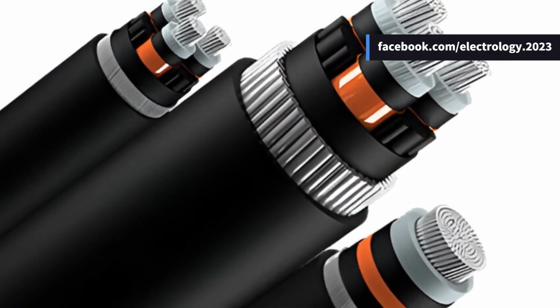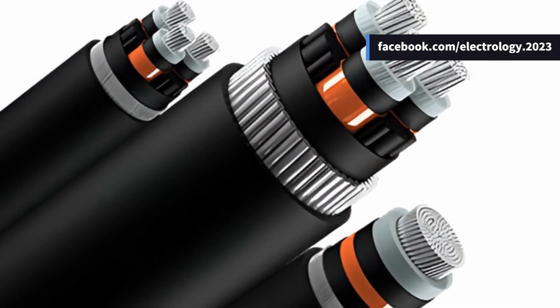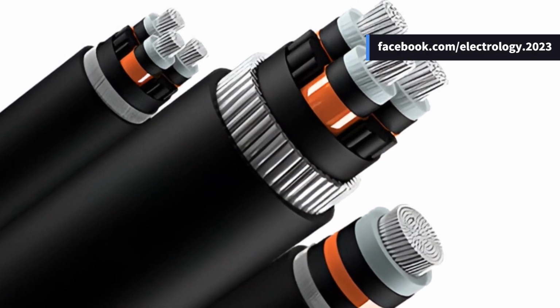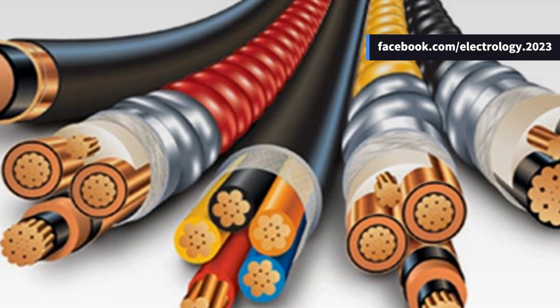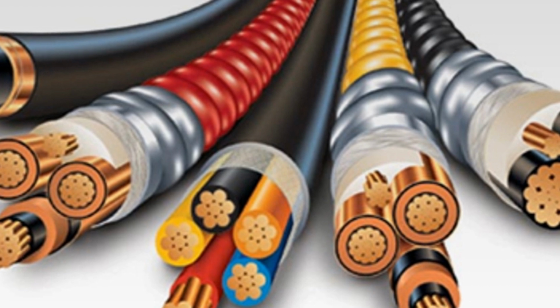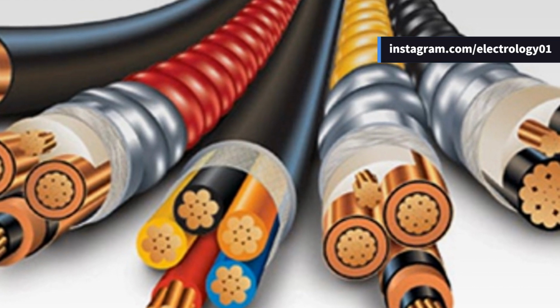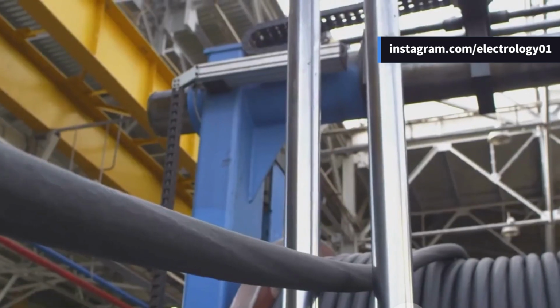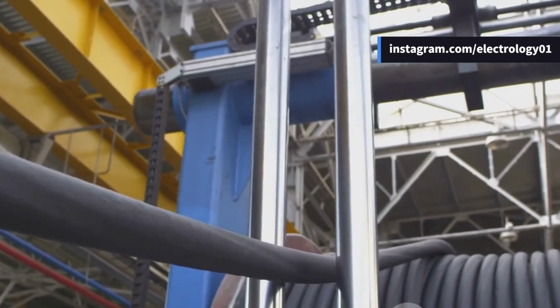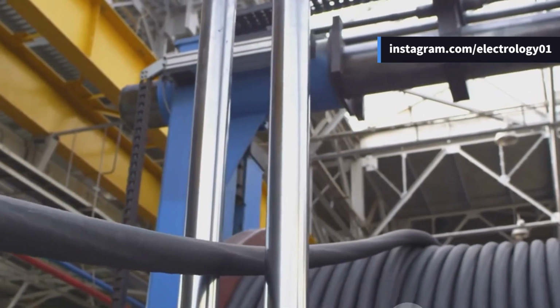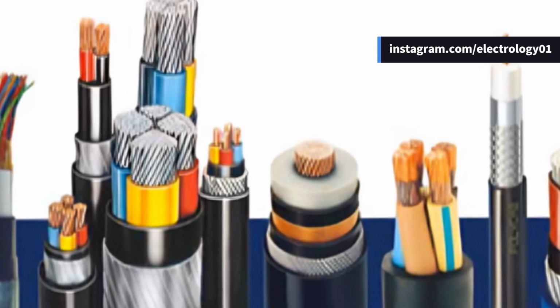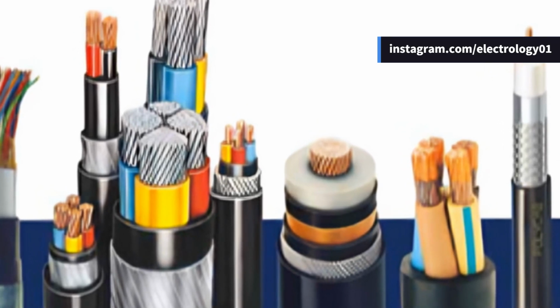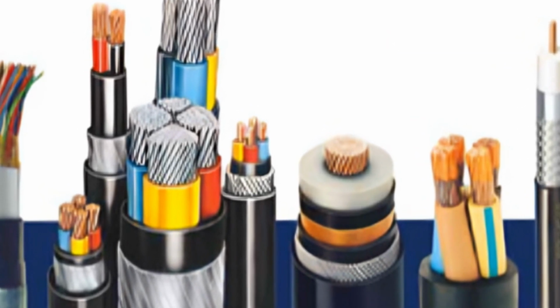So, in most practical systems, 3-phase power is required, and cables are designed accordingly. For voltages up to 66 kilovolts, 3-core cables are preferred because they are economical and compact. But beyond that, they get bulky and heavy, so single-core cables are used instead. There are 3 main types of 3-phase cables: belted, screened, and pressure cables.